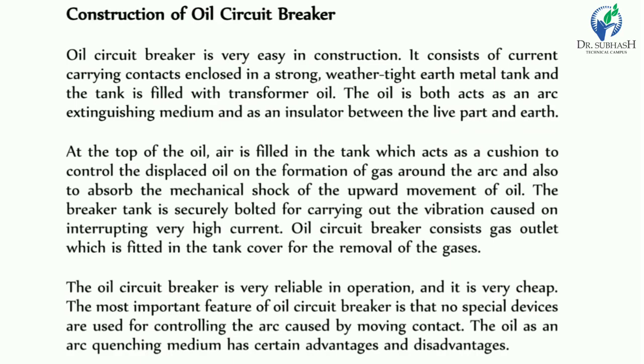It consists of current carrying contacts enclosed in a strong weather-tight earthed metal tank. The tank is filled with transformer oil. The oil acts as an arc-extinguishing medium. Air is filled on top of the tank, which acts as a cushion to control the displaced oil in the formation of gas around the arc.